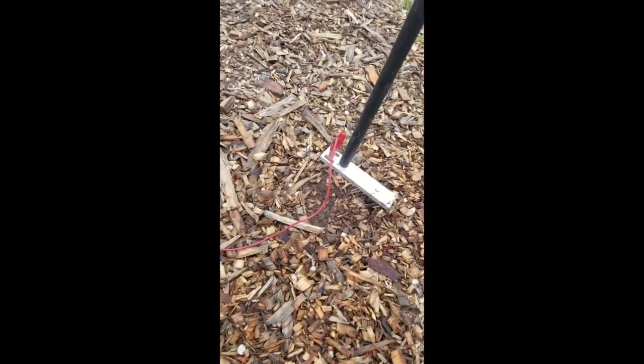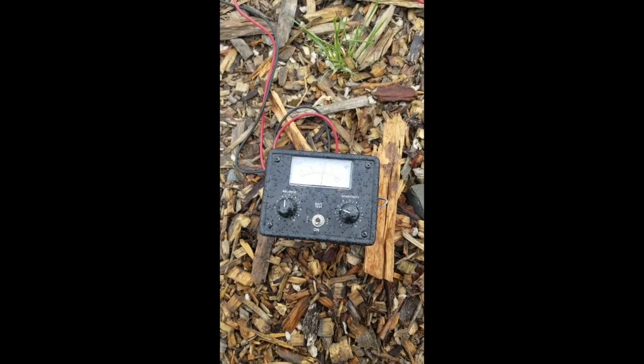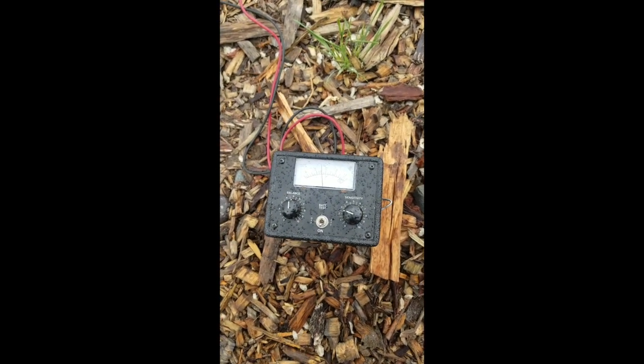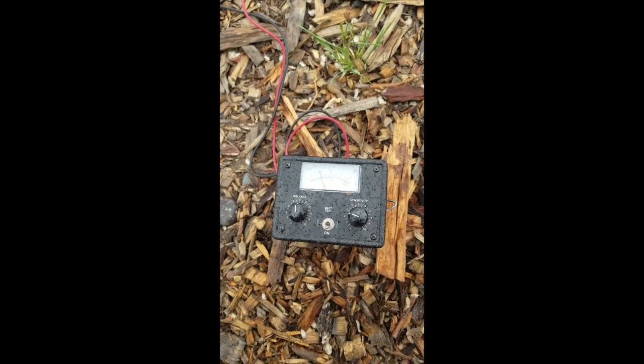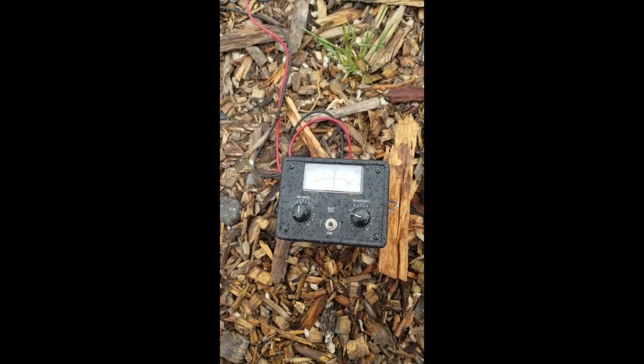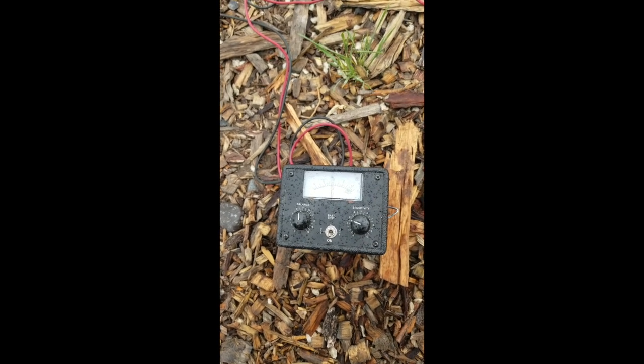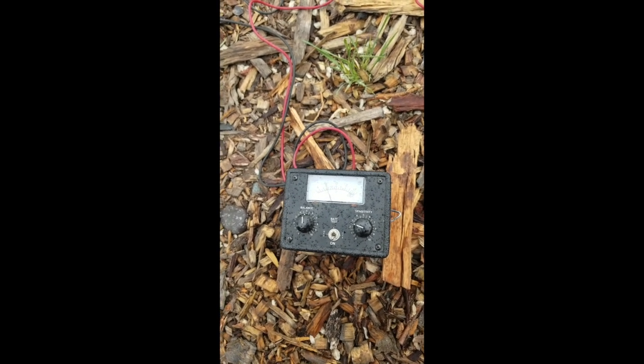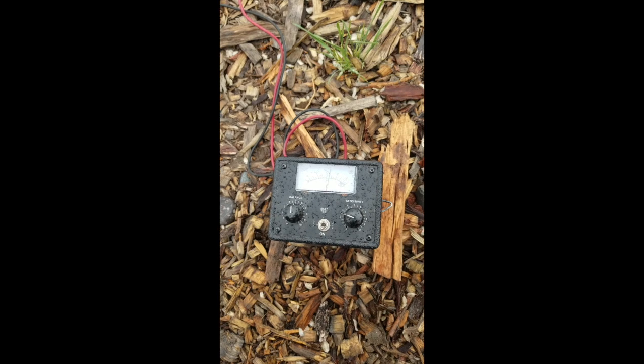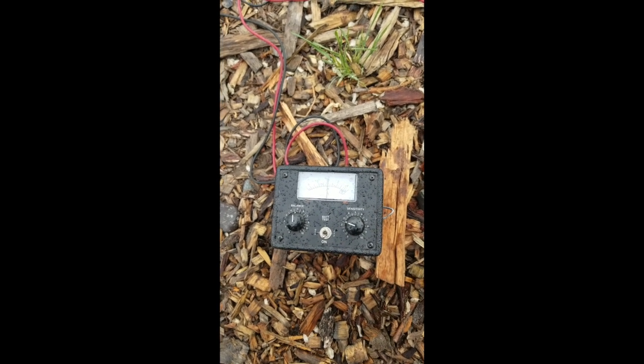I've placed my black probe where the red one was. Move my red probe out here. I'm getting a little bit stronger reading. I actually turned the sensitivity down a little bit. With our detectors having an analog meter, you only pay attention to the initial deflection. Nothing beyond that, until it comes back to 0, do you want to pay attention to. If an analog meter moves to the right, it's going to move to the left as a bounce back. So just pay attention to the initial deflection, and that only.